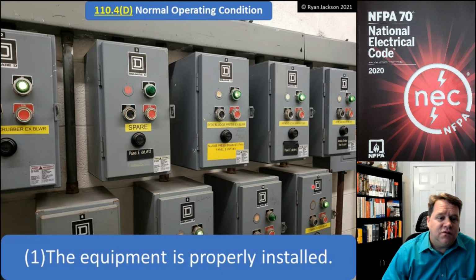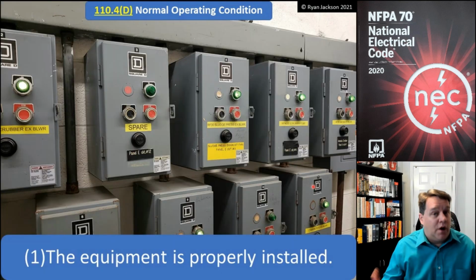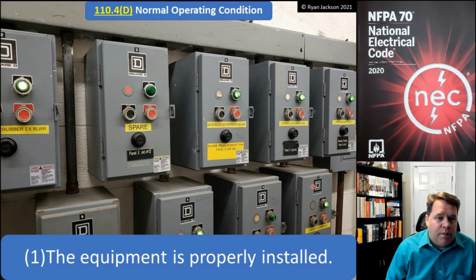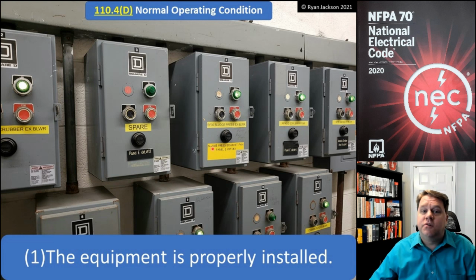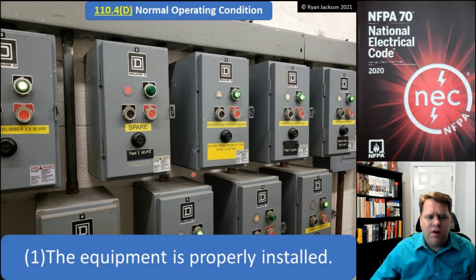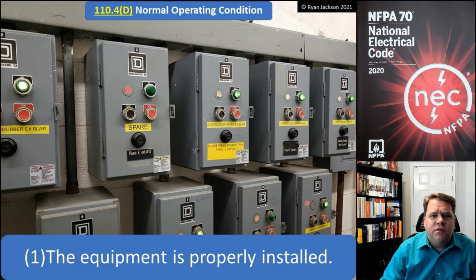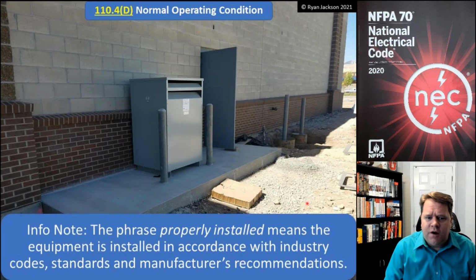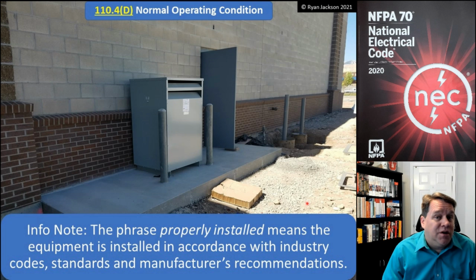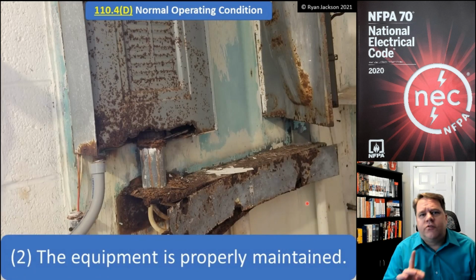Now, what that means is that the equipment is properly installed. Looking at this equipment, it appears that it's properly installed. So can I go up there and hit the stop and start and reverse and the hand-off-auto and things? Sure, assuming that it's properly installed. And of course, there's an informational note that says, look, when we say properly installed, we mean the equipment's installed in accordance with industry standards, codes, manufacturer's recommendations, and instructions. I think we know what properly installed means. It also has to have proper maintenance.